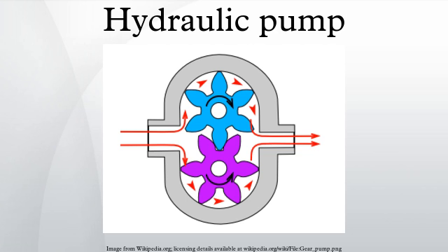It is preferred to have free flow to the pump. The body of the pump is often in open connection with the suction side of the pump. In case of a closed system, both sides of the pump can be at high pressure. The reservoir is often pressurized with 6 to 20 bars boost pressure. For closed-loop systems, normally axial piston pumps are used. Because both sides are pressurized, the body of the pump needs a separate leakage connection.